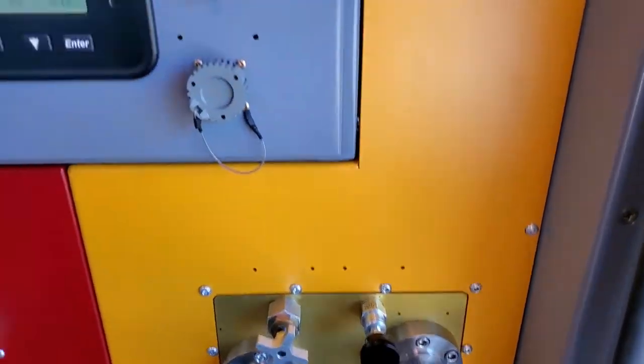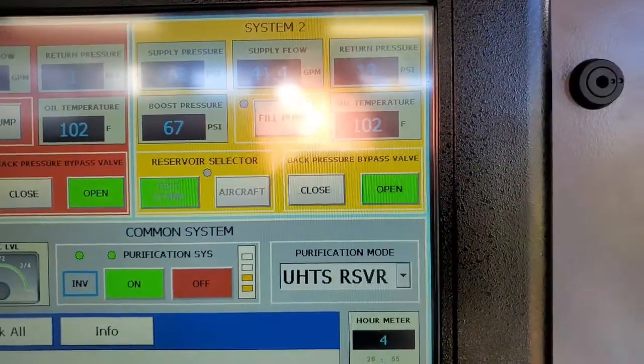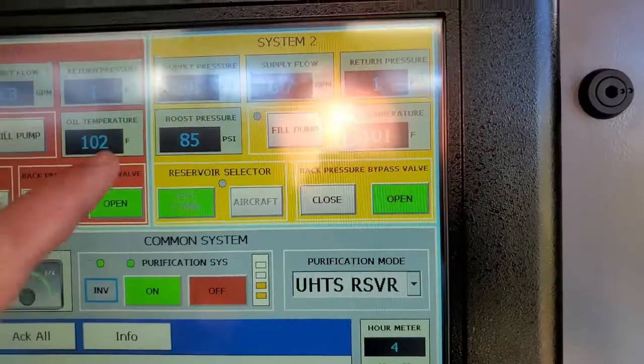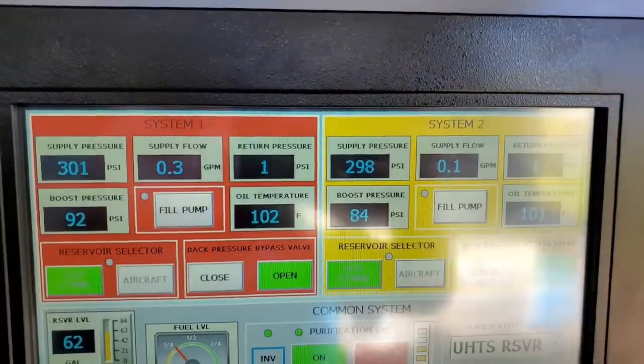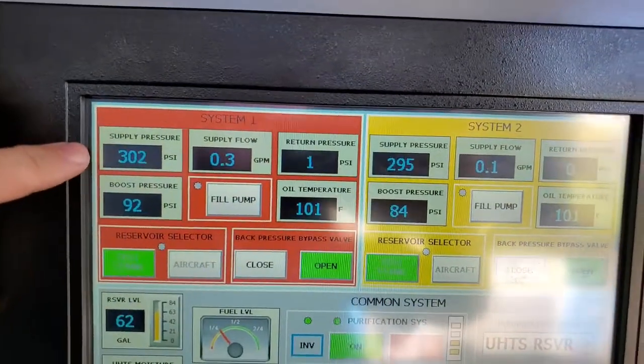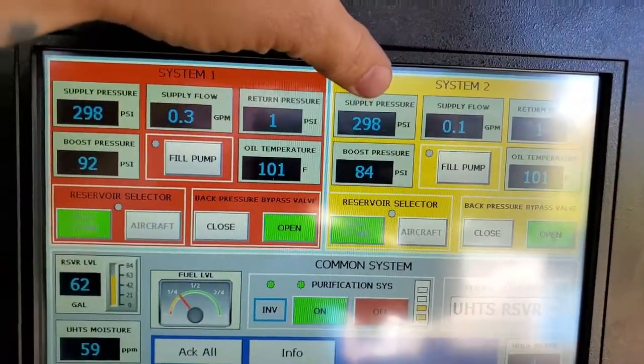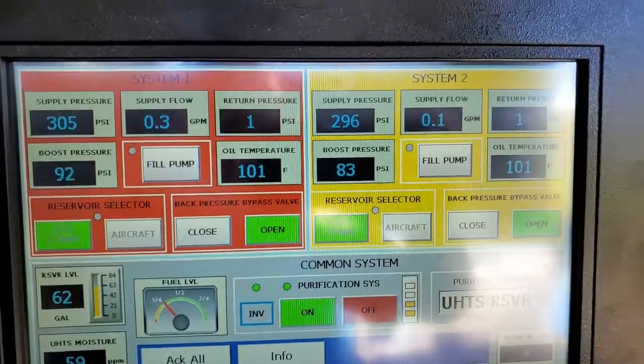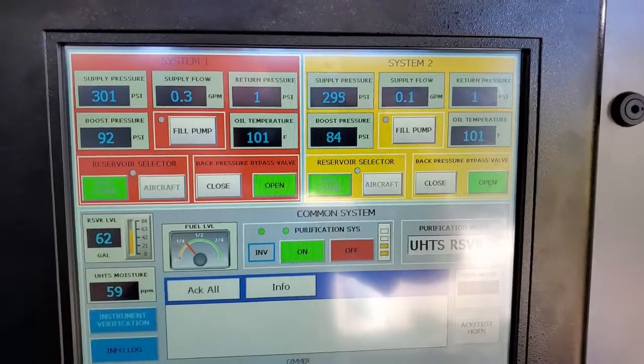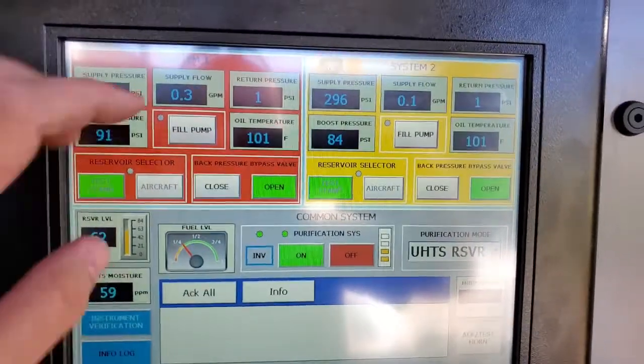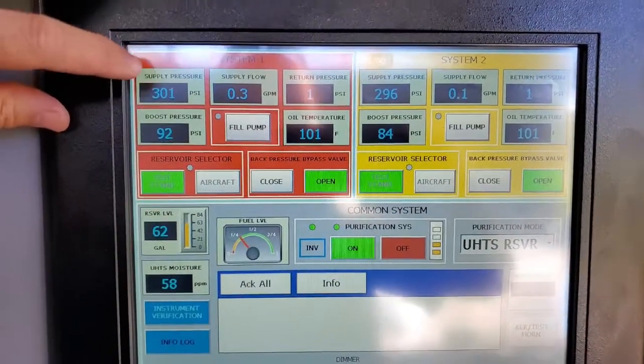We'll go ahead and close both System 1 and System 2 bypass valves. You'll notice the same increase on both systems. The pressures may not be exact, but those are good pressures. I mentioned standby pressure on the main pumps. Without standby pressure, you will not be able to build pressure on the systems. Now we're ready to build pressure on System 1.